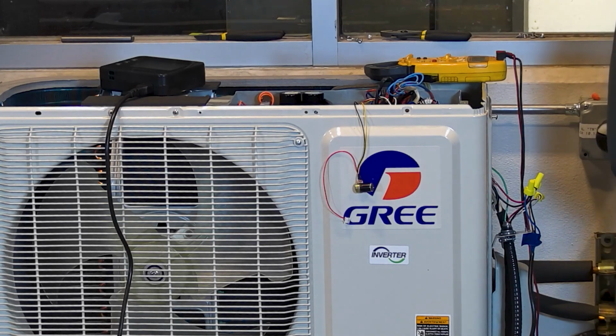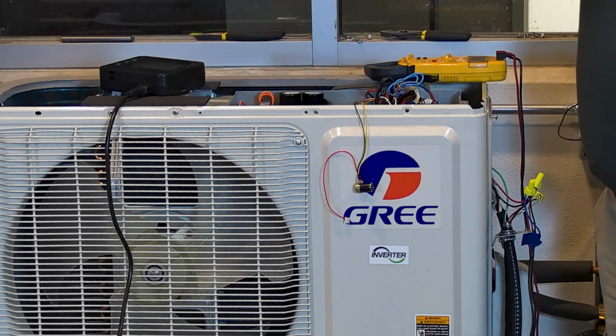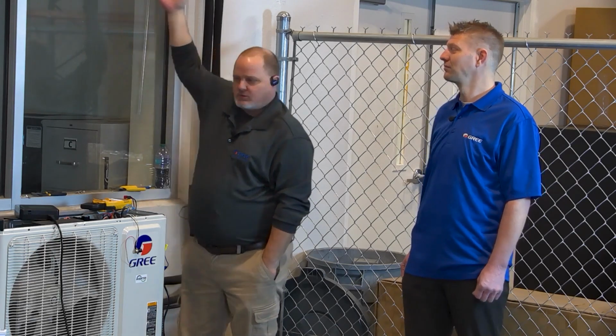If it's not, then I can go right to that head and hook it up there and see if I can simulate the outdoor unit and make the head run. If I can, then I know there's a problem with that cable between the two. Yep. It's a fail-safe way.